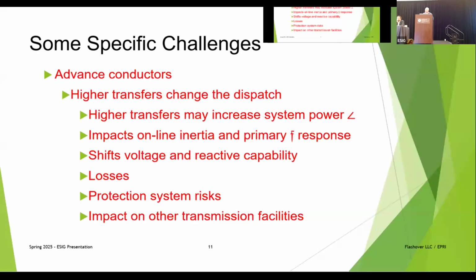If I put in advanced conductors and increase transfers by 2,000 megawatts, what does that mean? I may be running 2,000 megawatts more of inverters at the sending end, and I might dispatch offline 2,000 megawatts of synchronous machines at the receiving end. What happens to my system? There's losses. Voltage control, losses in the reactive sense too. Let's not forget there's Q losses here involved, and how does that affect operations?